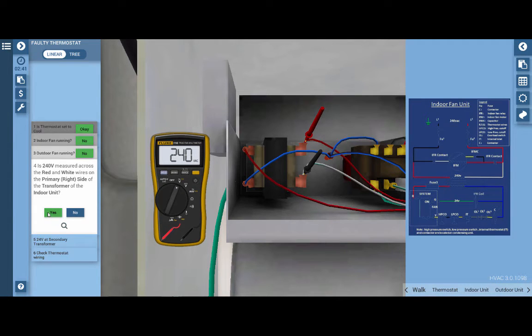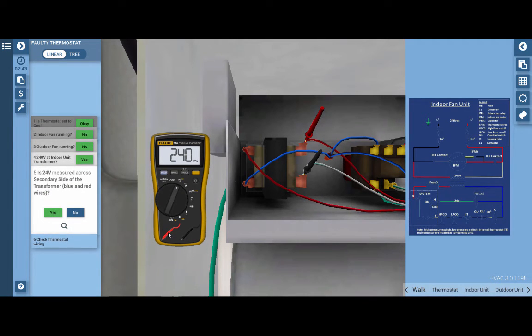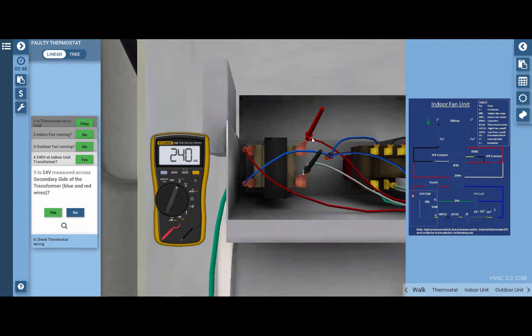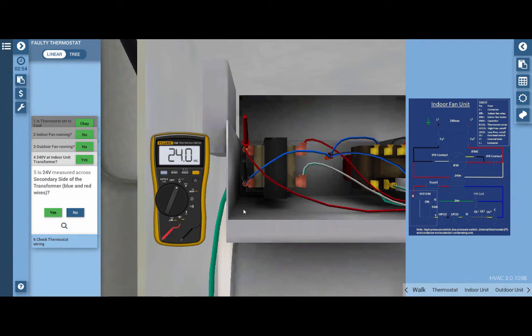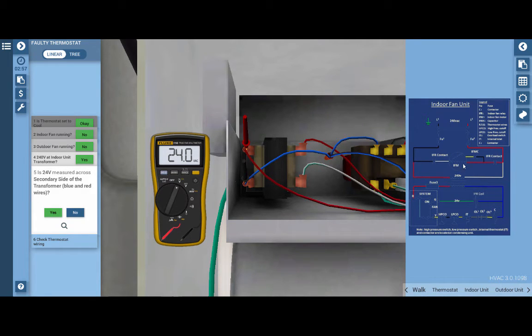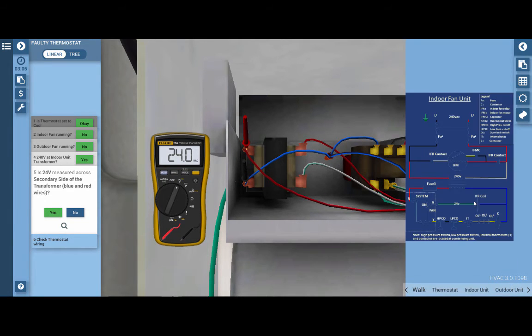So we do, in fact, have 24 volts. Our next step is to measure the 24-volt side of the transformer and verify that we have 24 volts coming out of the transformer. So if we just simply move the leads over to the red and blue wires here, we can see that we have 24 volts. So let's go back to this wiring diagram here for a second. We've verified 240 volts at this point. We've verified 24 volts at this point.